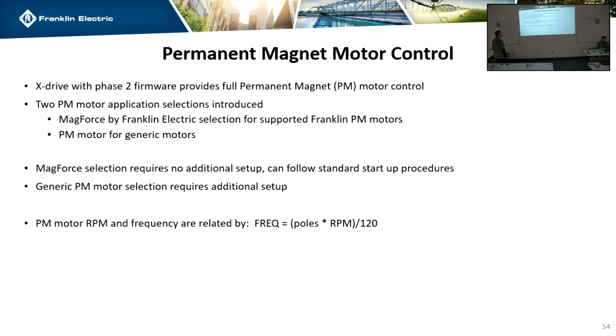Okay, so for the permanent magnets, it's just the kind of next wave of motor control. They're more efficient. They're coming. It's going to be a slow transition for all sorts of different areas depending on where you're at. Franklin, the reason this is in this particular model is we have an in-house permanent magnet motor for submersibles that's released. So we needed the drive to be able to handle it.